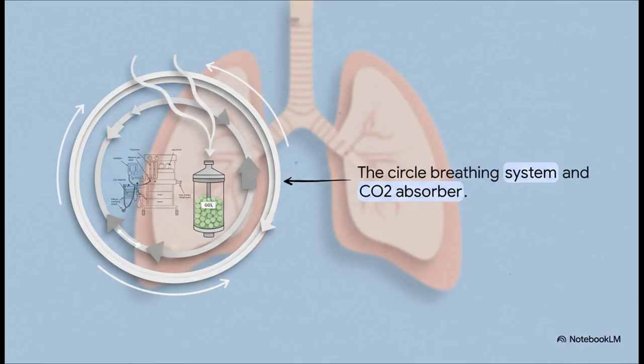And honestly, one of the smartest engineering features of the entire anesthesia machine is something called the Circle breathing system, to save these super expensive anesthetic gases and also to keep the patient's airway nice and warm. The exhaled breath isn't just vented away into the room. Instead, it gets pushed through a canister filled with a chemical called soda lime. The soda lime actively scrubs the toxic carbon dioxide right out of the exhaled breath. This brilliant little loop allows the pure oxygen and the expensive anesthetic vapor to be safely rebreathed by the patient, just going round and round in a circle.